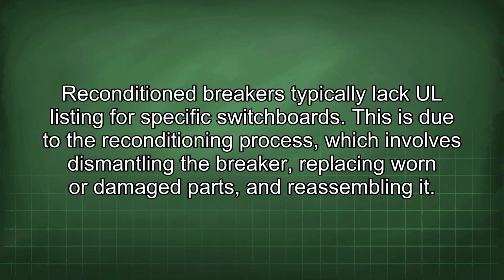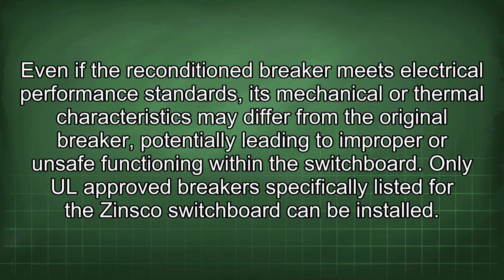Reconditioned breakers typically lack UL listing for specific switchboards. This is due to the reconditioning process, which involves dismantling the breaker, replacing worn or damaged parts, and reassembling it. Even if the reconditioned breaker meets electrical performance standards, its mechanical or thermal characteristics may differ from the original breaker, potentially leading to improper or unsafe functioning within the switchboard. Only UL-approved breakers specifically listed for the Zinsco switchboard can be installed.